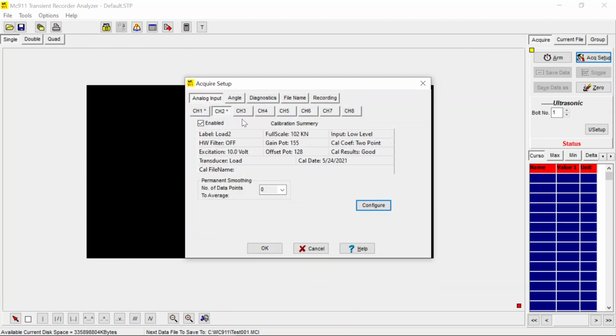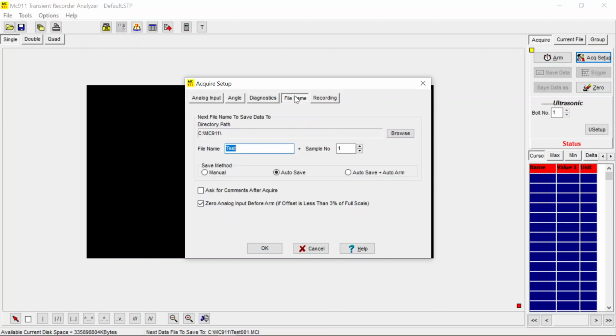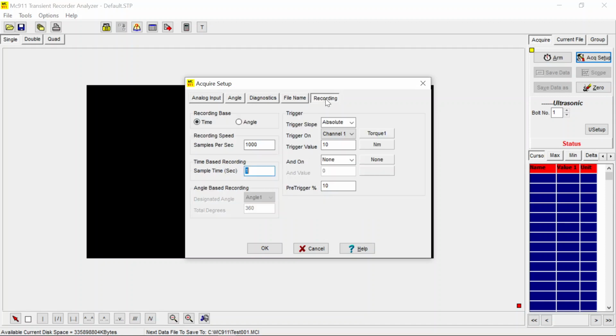So we enabled those two channels. File name, let's call this test. Let's call it UCF, for instance. Channel 1, and the same parameters, recording, same again. I set it for 5 seconds of recording. Okay, here we set up our analog signals. Now we go set up our ultrasonic channel.